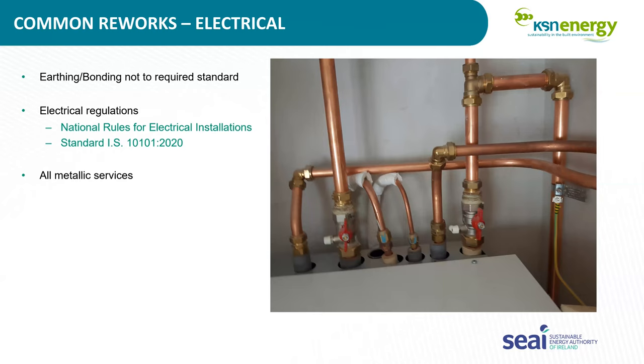Earthing and bonding, this is one that comes up a lot. For an SEAI installation, SEAI ask that all the earthing and bonding is done to the National Rules for Electrical Installations, IS 10101:2020. And typically, whilst there's an earth on that cable, we would ask that all the cables are cross-bonded and linked together.